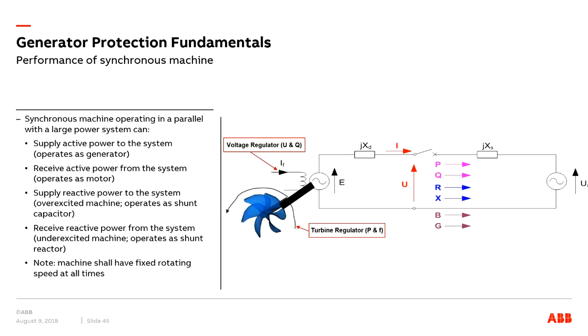Now, before we move on to the other protections, which I will navigate through pretty quickly, you need to understand the different operation conditions. The synchronous machine operating in parallel with a large power system can supply active power to the system. Then it operates as a generator. If it receives active power from the system, it operates as a motor. It supplies reactive power to the system in an overexcited machine. Then it operates as a shunt capacitor. If it receives reactive power from the system, it's an underexcited situation. And it may be noted that the machine will have a fixed rotating speed at all these times.